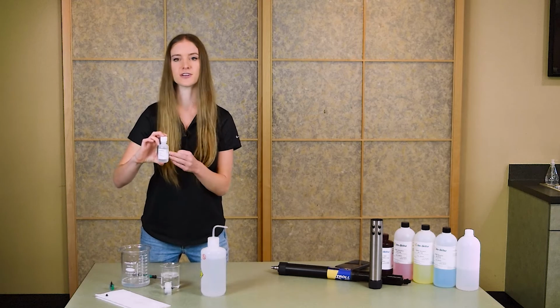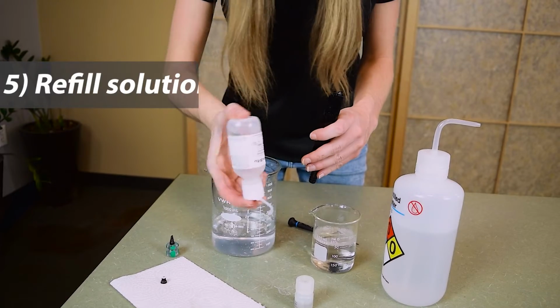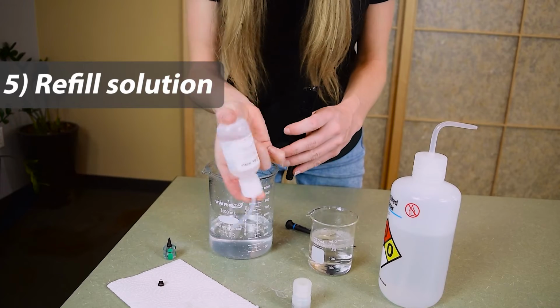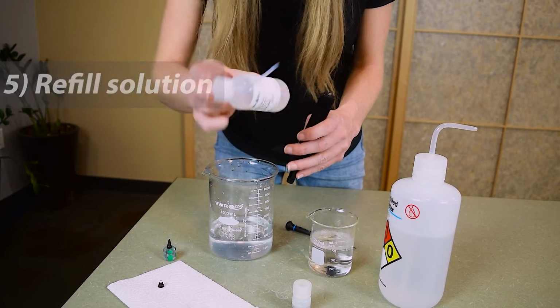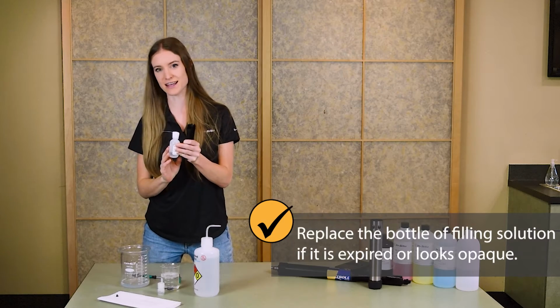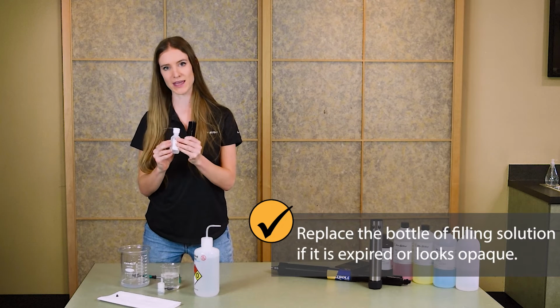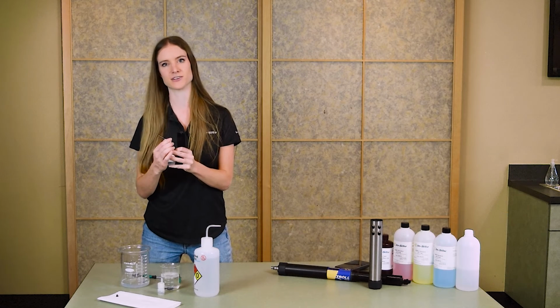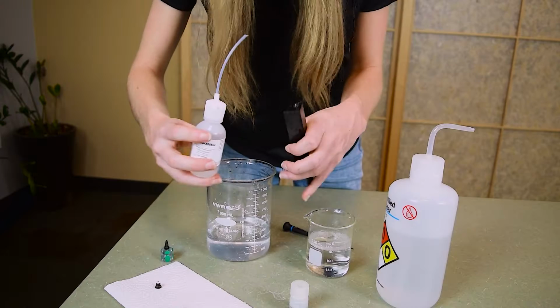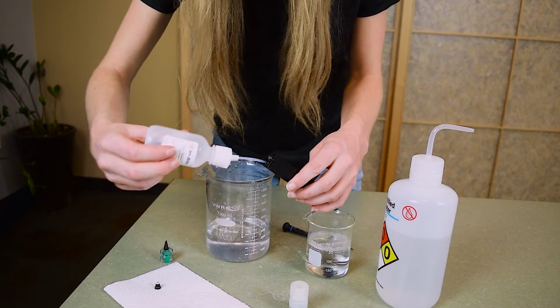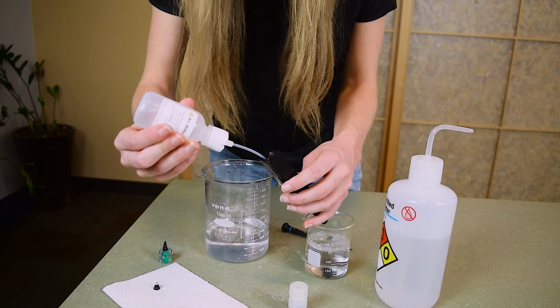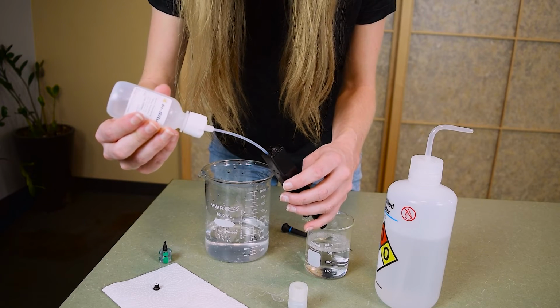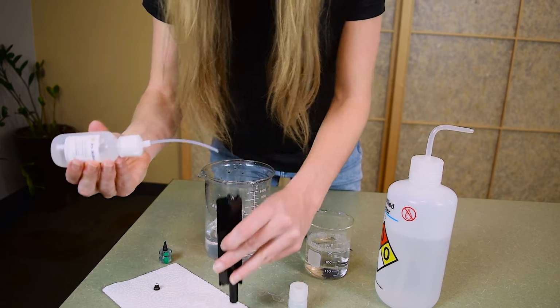To refill the solution, first mix the solution by inverting it gently 3 to 5 times without introducing any bubbles. It's okay if the solution is slightly cloudy, but if it's looking milky or opaque, it's time to get a bottle of fresh solution. Open the bottle of fill solution and then insert the tube into the bottom of the reservoir. And you want to fill it up while slowly removing the tube from the reservoir.